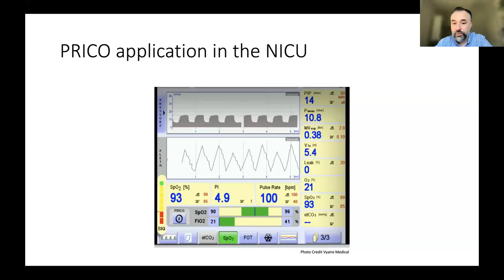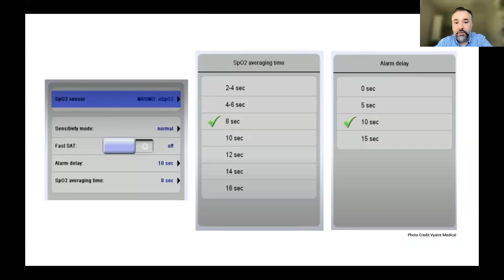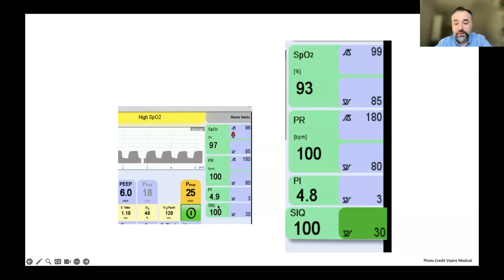One important element, because on the screen you can see the plethysmographic curve, but on the left here you can see the quality of the signal. That can be helpful if you have some problems with the reading. So it will be additional information, and if the signal is too low, the system will switch off. Some of the parameters that can have influence on how the system works. So something that I mentioned before, the averaging time, also the alarm delay that I mentioned in the introduction, monitored values that you can also see, not only signal quality, but you also have the perfusion index here on the screen.